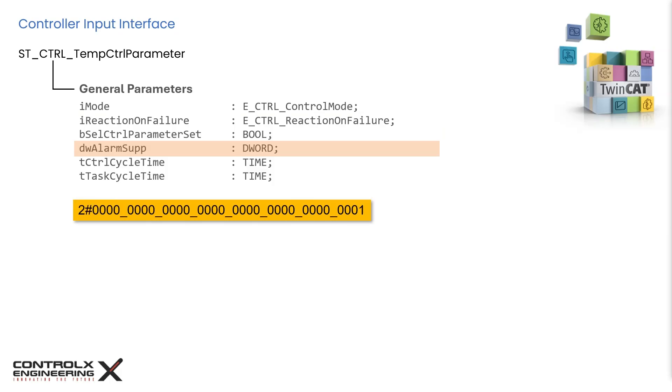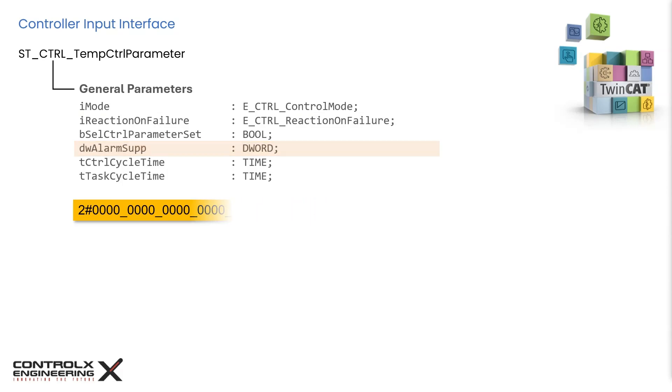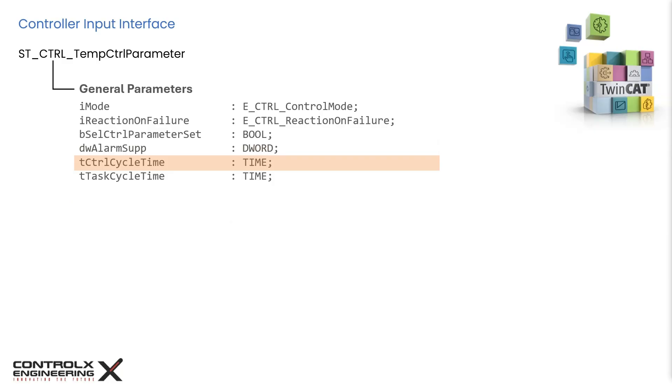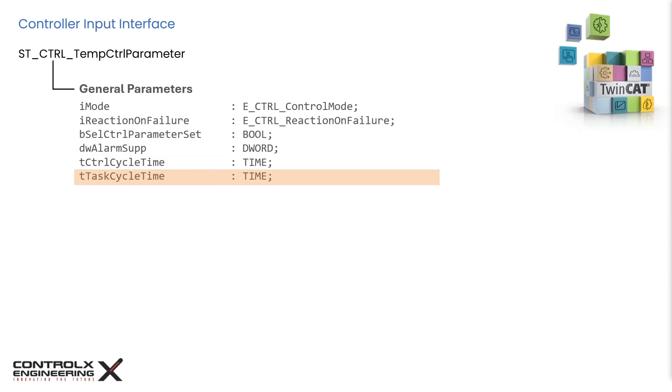Alternatively, setting all bits to one will suppress all alarms. The complete list of bit masks is available in the controller documentation. This input is for specifying the controller sampling time in seconds. The controller will use this time to sample input feedback value, evaluate the PID controller, and calculate the outputs. Using this input we inform the controller of the PLC task cycle time. The controller function block is called with this time interval.